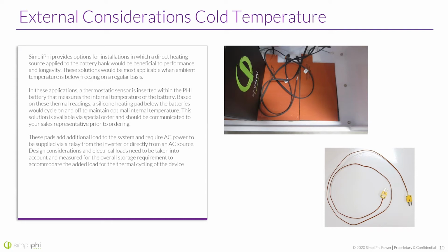So SimpliPhi provides options for installation in which a direct heating source applies to the battery bank. So again, this is really to heat the battery. The batteries just sit right on here. This will heat up the battery, and it actually has a thermostat connected to it. So it knows the temperature, and it can actually measure the internal temperature of the battery. And based on these thermal readings, the heating pad will turn off and on to make sure the batteries stay within a specified window. These pads, though, they do add a lot of additional load and require AC power to be supplied via a relay from the inverter or directly from an AC source.